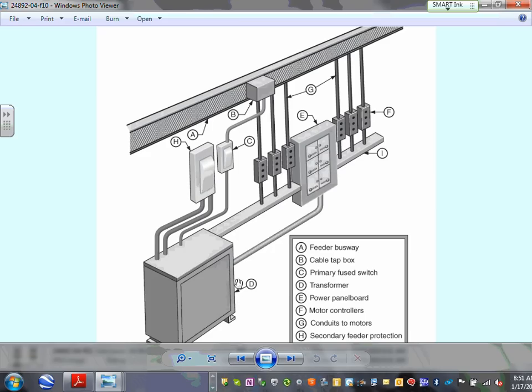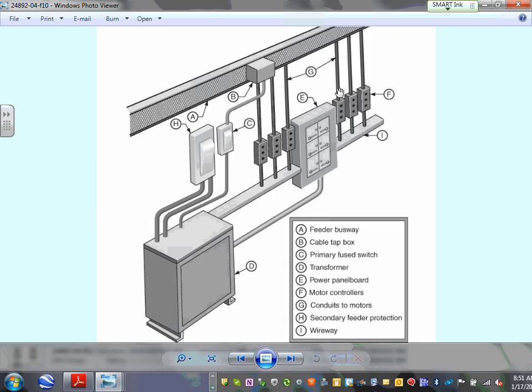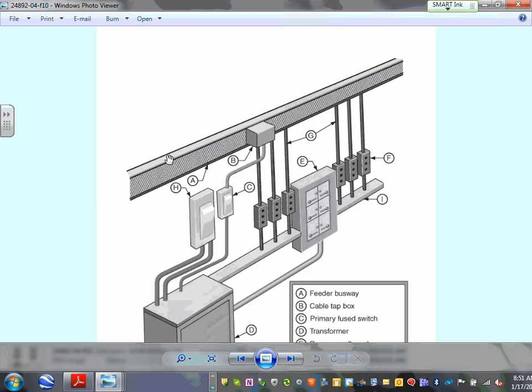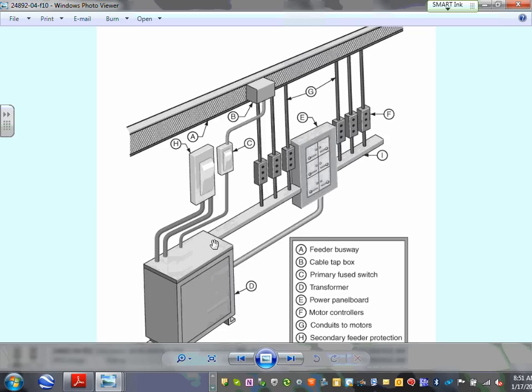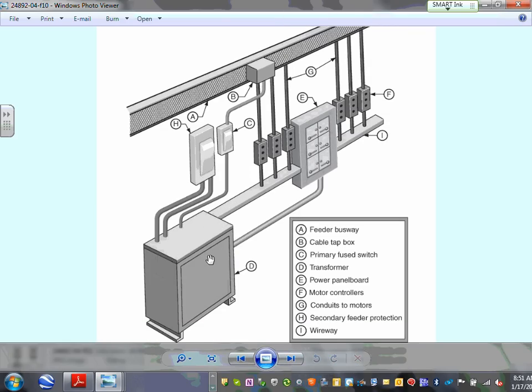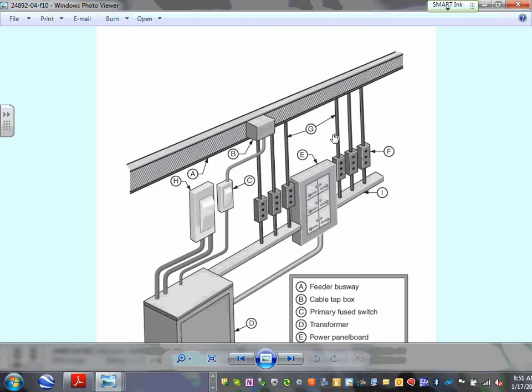D is the transformer, like I said. D is a transformer, primary. Power panel. Motor controller is F. They have a bunch of motor controllers also coming out of these Fs. We have I, a wireway feeding these motor controllers, coming directly and going somewhere. Secondary feeder protection is H. That's the secondary of the transformer, and the wireway is that little deal here. So what they're doing is bringing power here, guys, tapping that power into a transformer. From the transformer, they're protecting primary and secondary, coming from the transformer into a panel. Out of that panel, they're taking a couple of motor controllers and feeding multiple motors. So where is this happening? Happening right in this project.